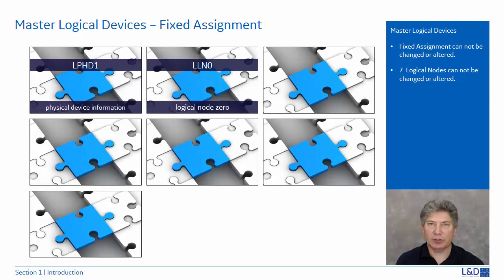Next is the LLN0, which is logical node 0, and it provides the status of the settings groups, the GOOSE and report control blocks, and data sets, and indicates the status of the relay, whether it's on, off, or in test mode. LGOS is used for GOOSE subscription monitoring, such as the RX GOOSE status and data associated with the subscription GOOSE configuration.